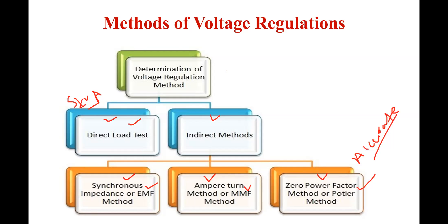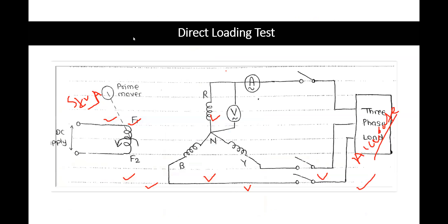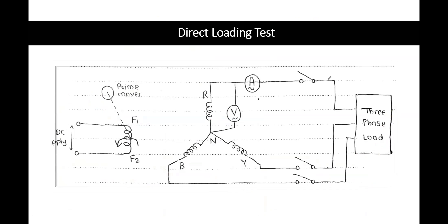In the direct loading test, observe this diagram — this is the arrangement to calculate voltage regulations. Here I connect directly a three-phase load to the alternator. This is your armature winding — R, Y, B star-connected armature winding, that is why neutral is present. Between each phase and neutral I connect a voltmeter, and the R phase is connected directly to the load. I provide switches so I can calculate full load voltage and no-load voltage.